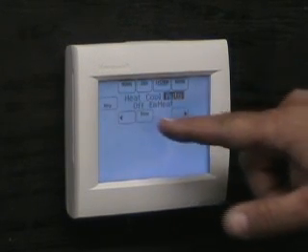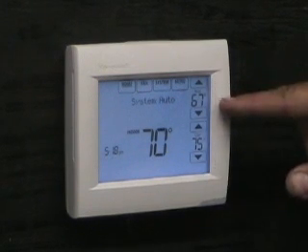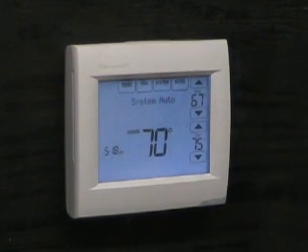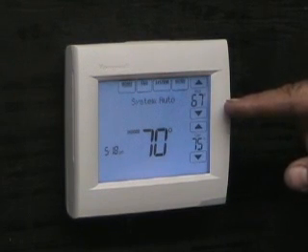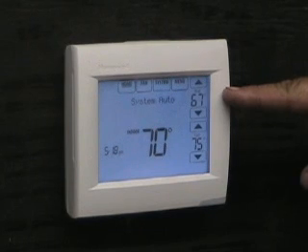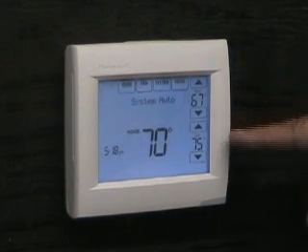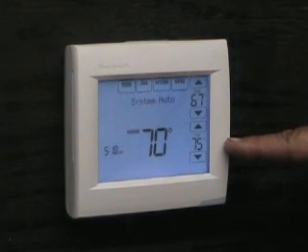In the auto mode, both the cooling and the heating temperature settings are displayed at the same time. If the indoor temperature falls below the heating set point, the thermostat will automatically energize the heating equipment. If the indoor temperature rises above the cooling set point, the thermostat will automatically energize the air conditioning.